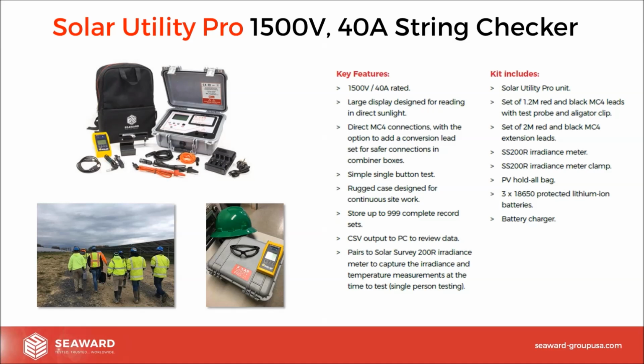But if you're dealing with larger scale plants, there are other challenges we have to overcome which traditional tools can't. First and foremost is the scale of utility scale solar PV plants these days. When we look at the architecture of the panels, we're looking at 1500 volt strings. Often those strings are paralleled into a single fuse, maybe a 30 amp fuse. So what we're dealing with is very different to a carport or a rooftop array, and we need something specific for that architecture.